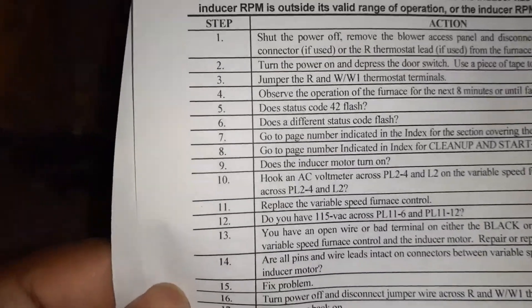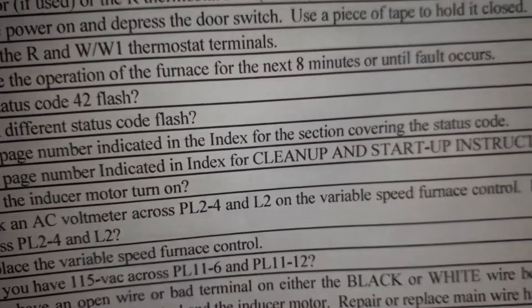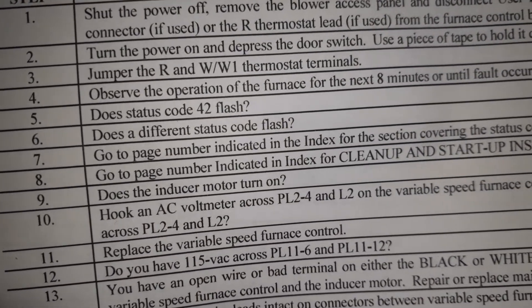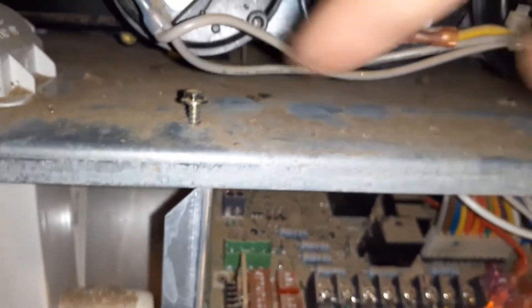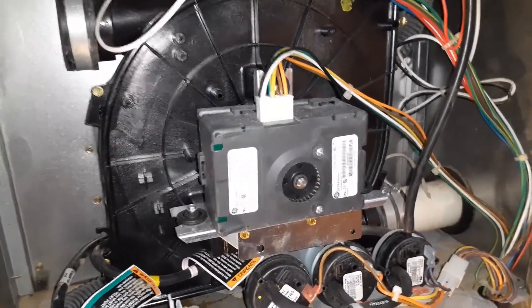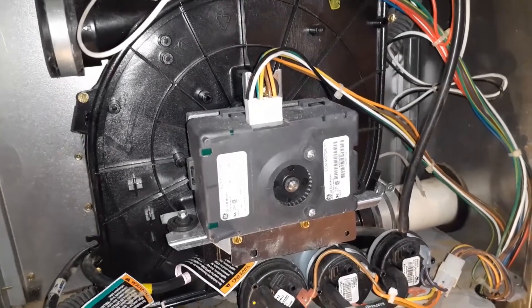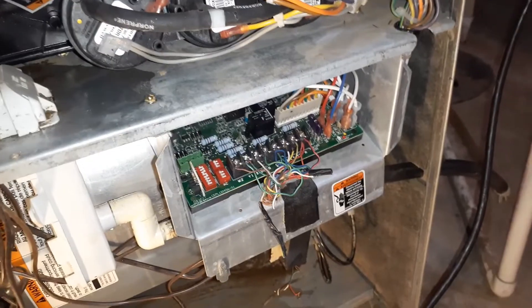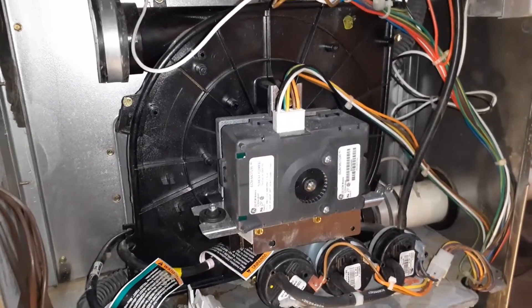The next step requires me to test the connections PL2-4 and L2 on the variable speed motor, because the inducer motor also didn't turn on. I'm going to do PL24 and L2. I'll remove this board — there's a screw here and a screw here. So error code 42 is the inducer motor not coming on. I wasn't sure whether the inducer motor was bad or the circuit board was bad. I did replace the circuit board but it didn't change anything, so the inducer motor was bad.